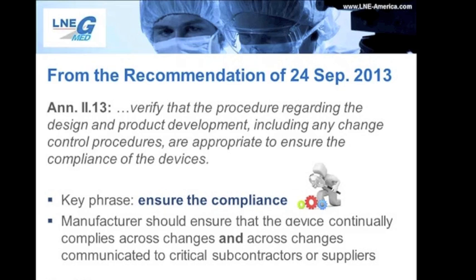This is where a lot of manufacturers have trouble with their contract manufacturers. A change is communicated, but the output doesn't match the input. So really try to avoid the game of telephone with your critical subcontractors and build your quality management system and procedures to really minimize it as much as you can. Now, I know that it's easier for me to say in my ivory tower of a notified body, and it's hard for industry to do. I get that. But keep in mind that it's not impossible.